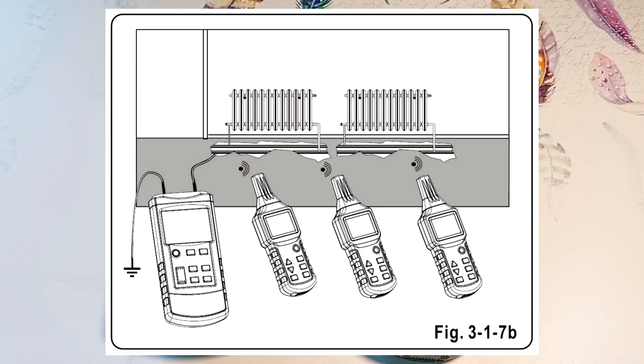This picture shows the detection of metal pipes in the wall and floor. These pipes must not be grounded. We connect one wire of the generator to the pipe, and the second to ground. We are looking for pipes in the same way as wiring.